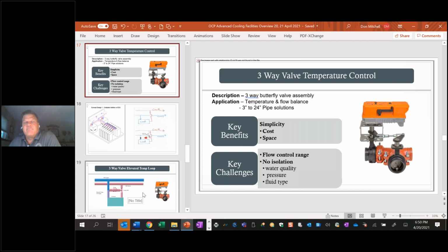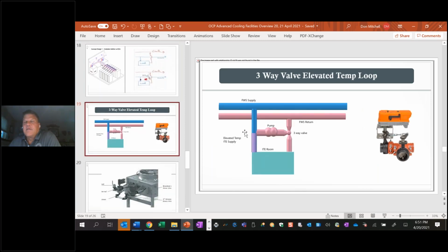This was a discussion we just had the past two weeks. The concept is, if all you're looking at doing is trying to keep the liquid going to your immersion tank above dew point, you could tap off a 20-degree centigrade line or 10-degree centigrade line, put in a heating loop, and then use that to distribute liquid, and you won't get condensation. Let me pause, does that make sense to anybody? Would anybody ever do that?